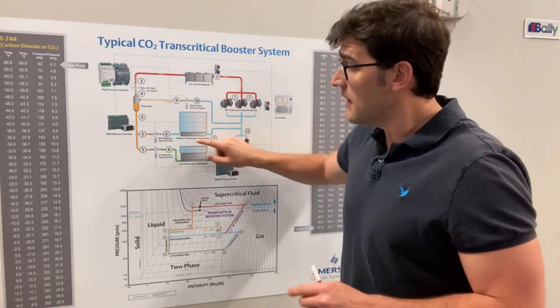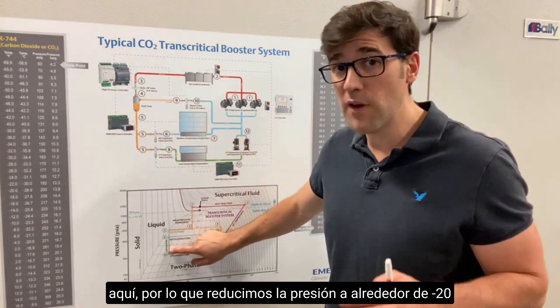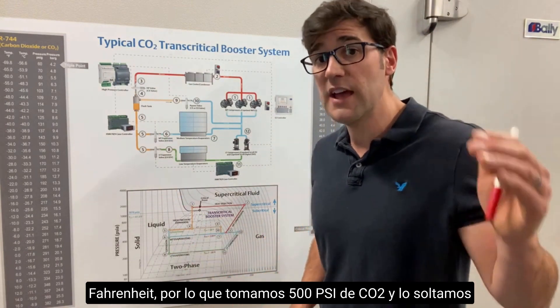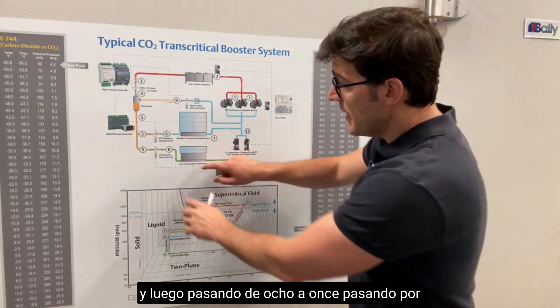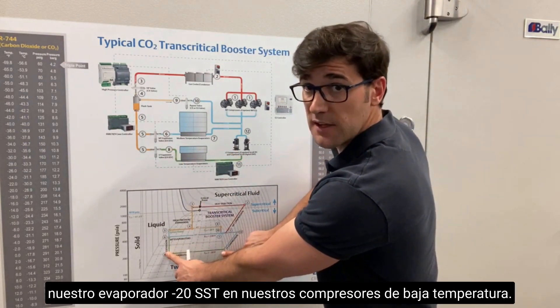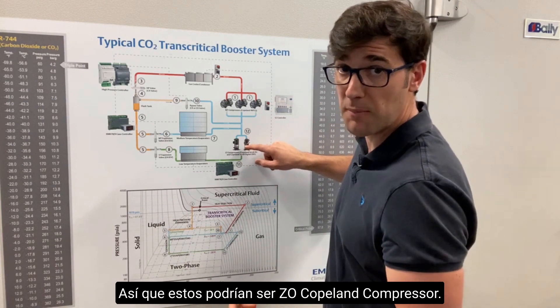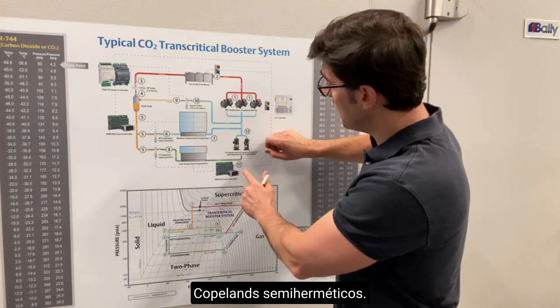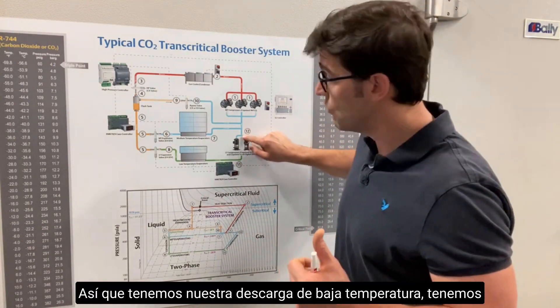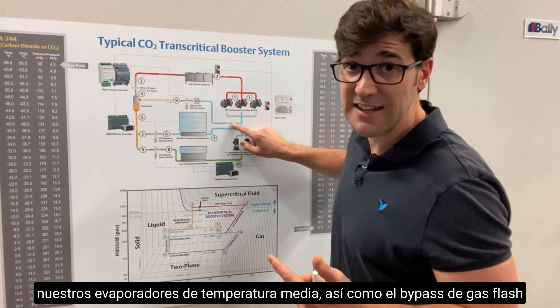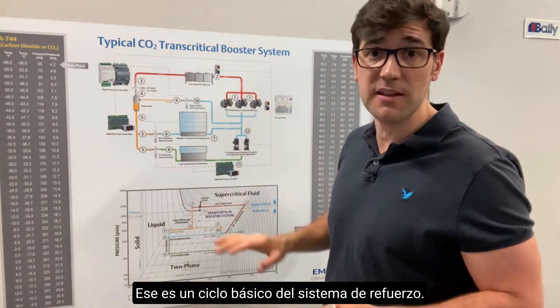From the flash tank receiver, we also feed the low temp metering devices, reducing the pressure all the way down to about 200 psi — from 34 bar down to 14 bar — corresponding to a minus 20°F SST. From 8 to 11, we go through the minus 20 evaporator into our low temp compressors, which could be ZO, Copeland, or 4MLS semi-hermetic Copelands. From 11 to 12 is the low temp discharge, which feeds back into the medium temp suction along with the medium temp evaporators and flash gas bypass. That's how it cycles — that's your basic booster system cycle.